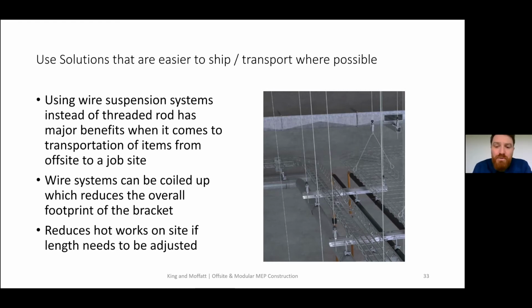You can make very quick adjustments to your uni struts on site if you need to, whereas if you cut a threaded rod, there's no real way to make quick adjustments afterwards. If you need to make it longer, you have to start looking for threaded rod joiners, which looks very messy. If you need to make it shorter, you have to start cutting it using angle grinders, and then you're into the use of hotworks permits. So these kinds of systems are hugely beneficial.